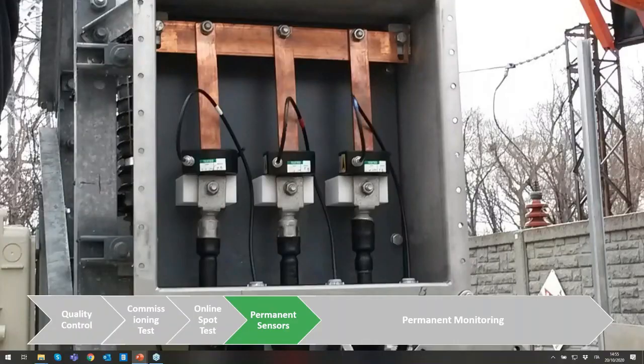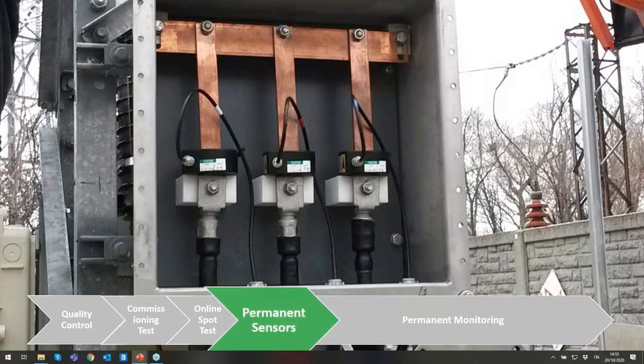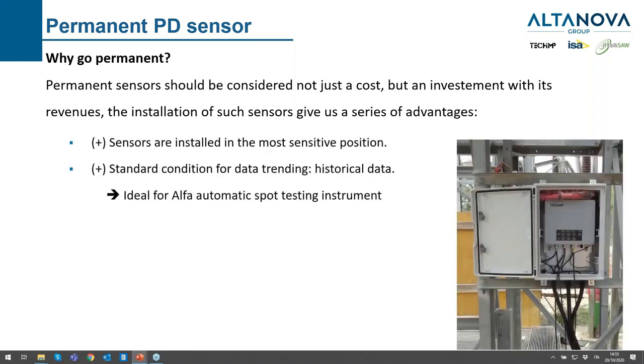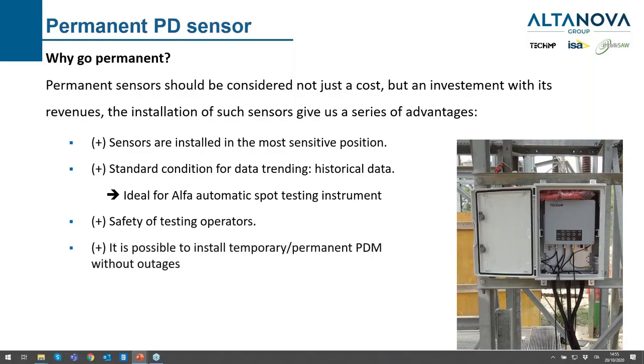The permanent sensor can be a very good choice when installing a new asset. There is an investment, but it's not a waste of money — we have many advantages. We have the possibility to install the sensor in the most sensitive position. We also have standardized testing conditions: if you want to compare data from different sessions, for example from 2008 with 2021, in some cases we have data more than 10 years old and we keep adding new data on the same sensor.